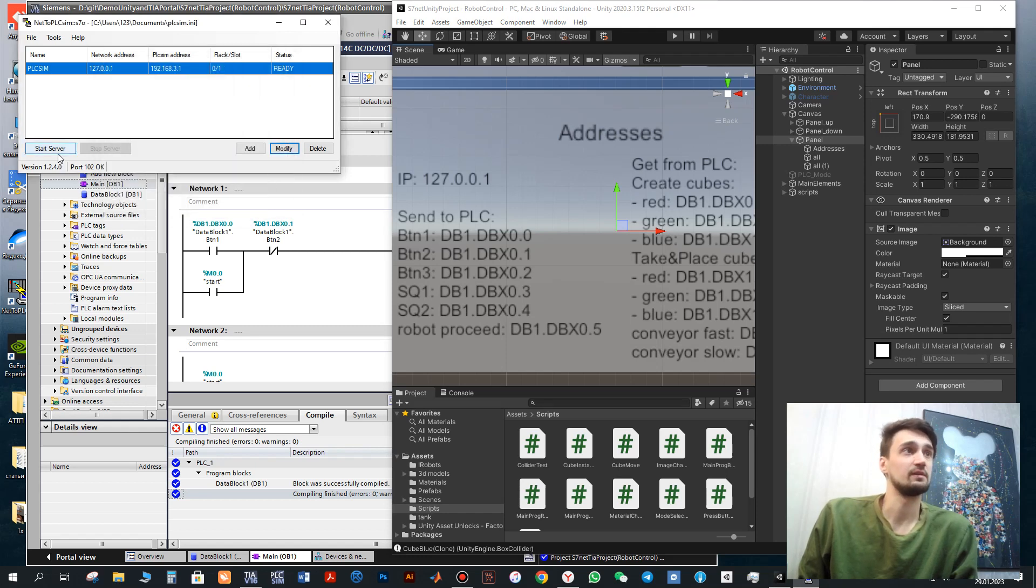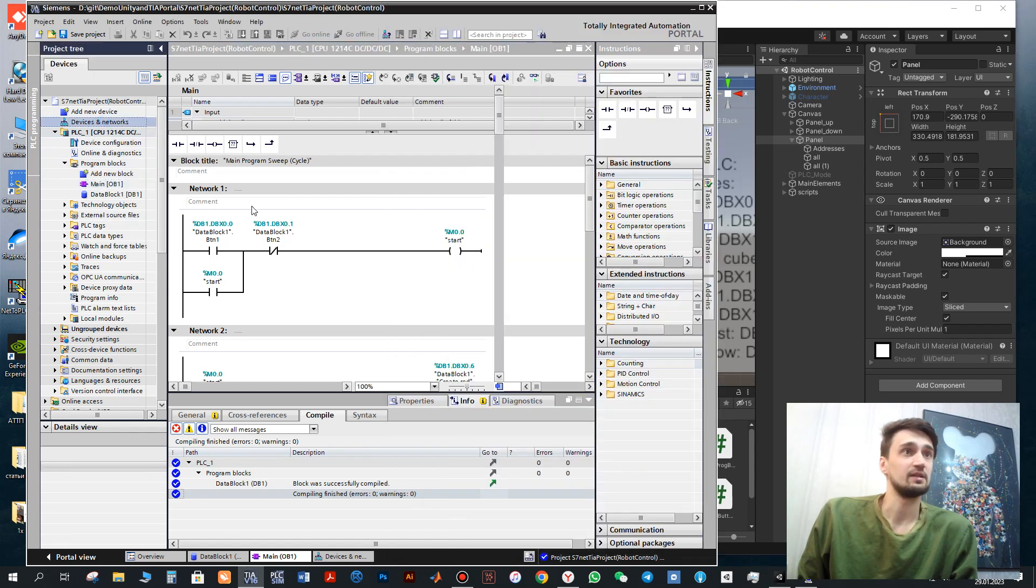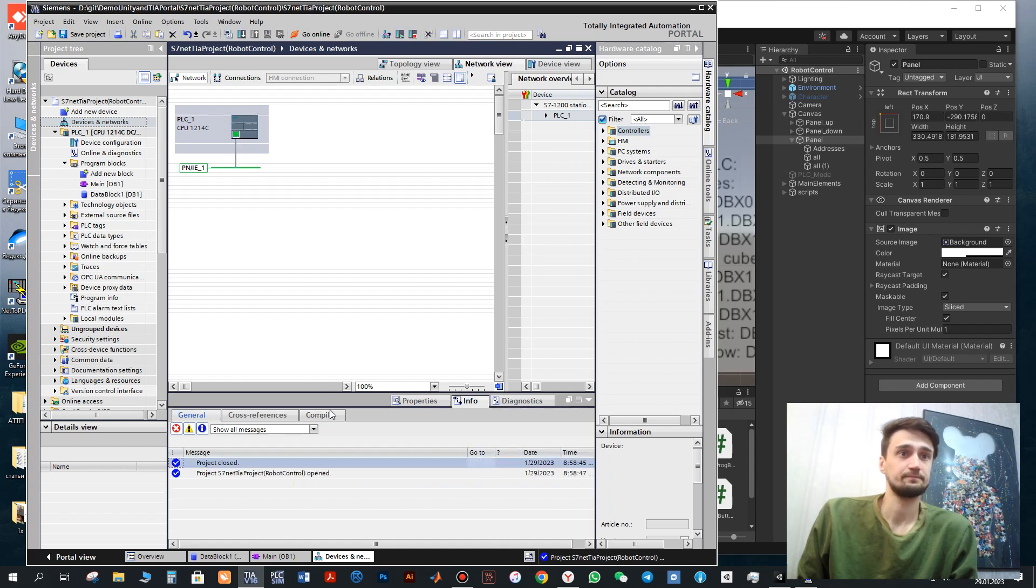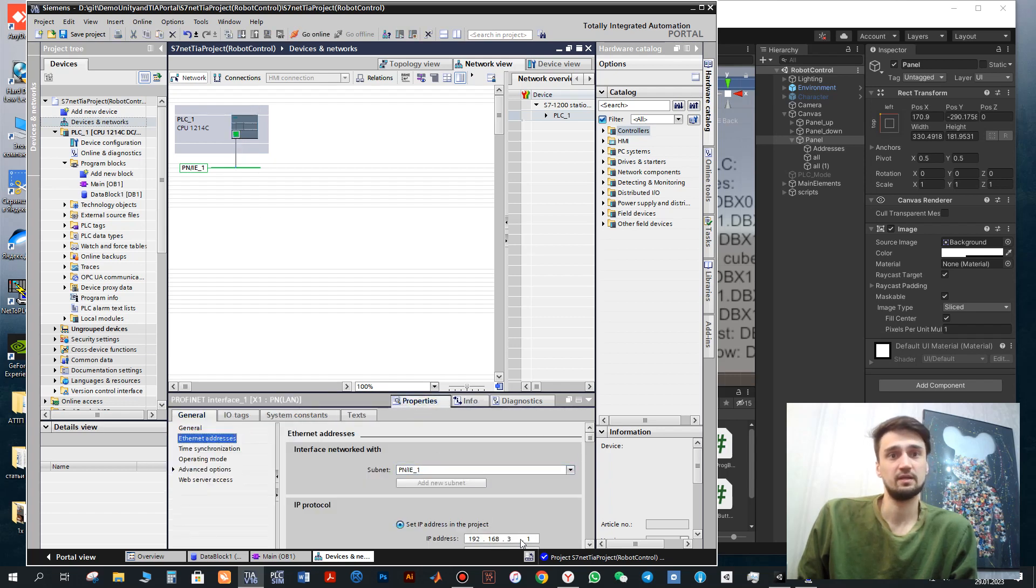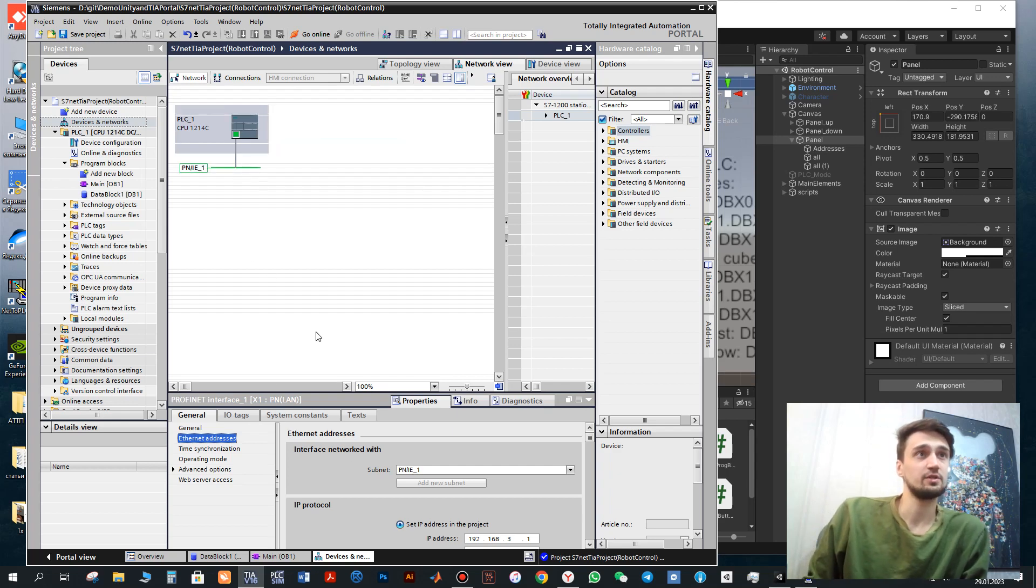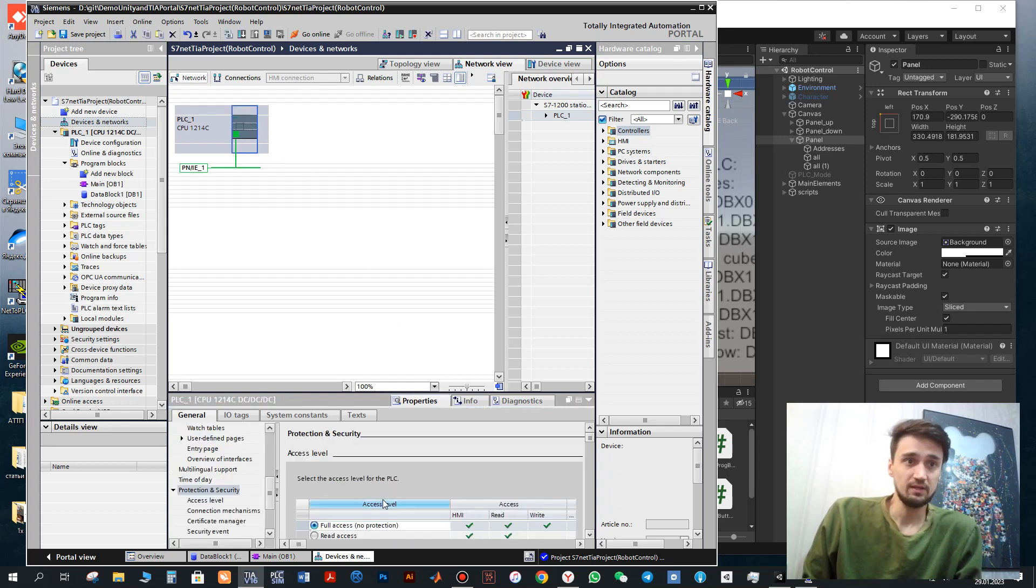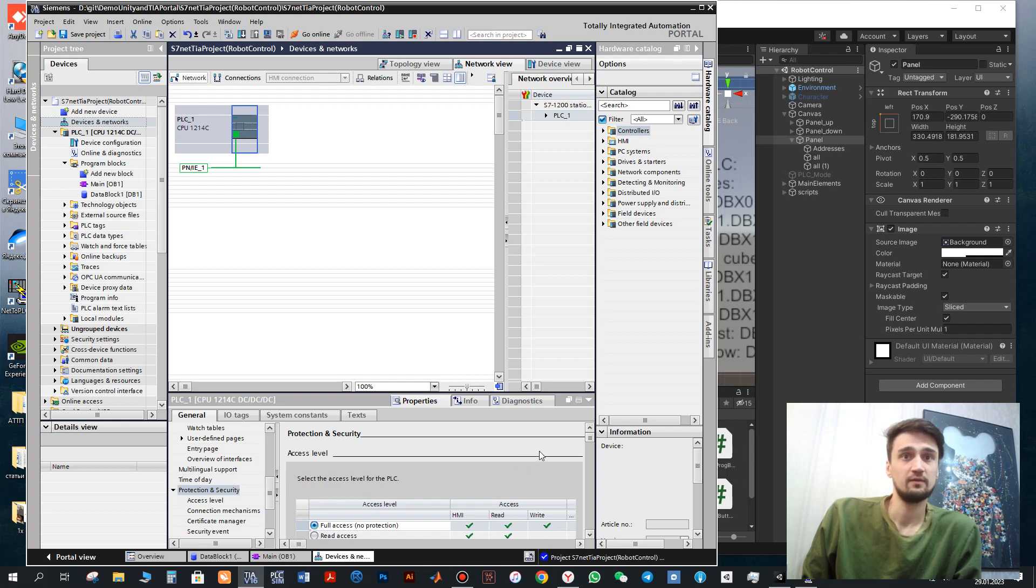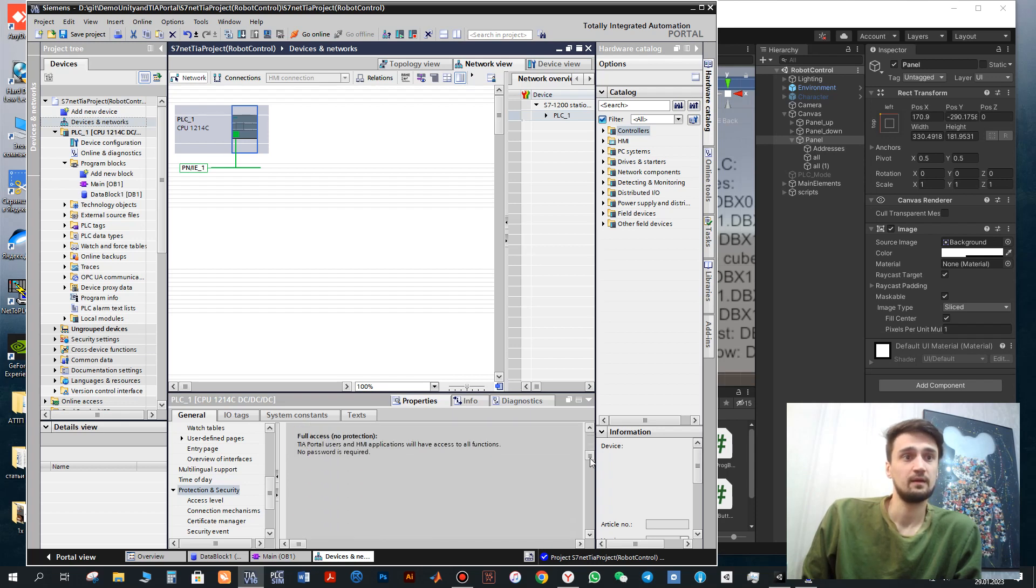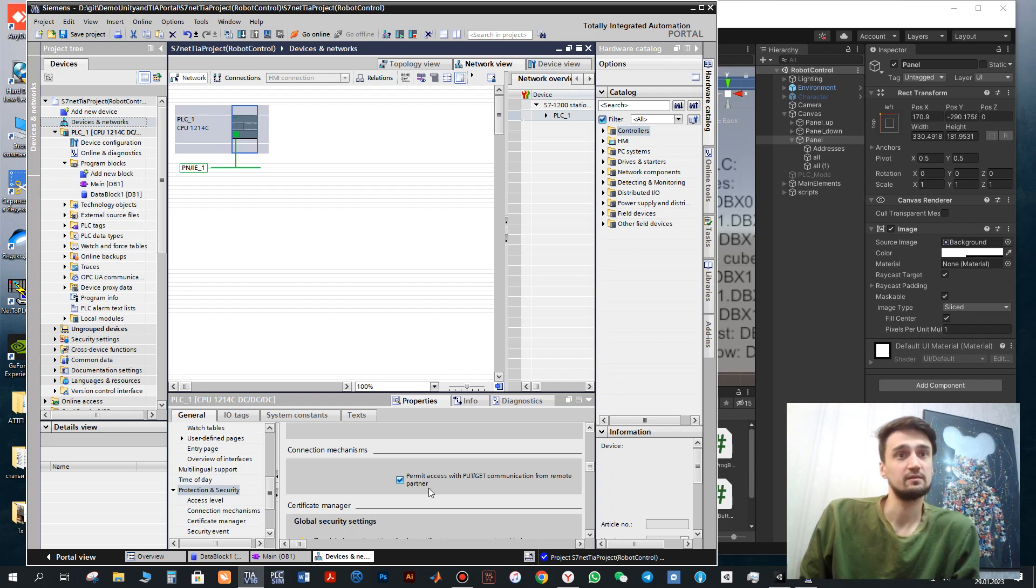After that we simply start this server. And address of the PLC you can check here: device and networks. So you set it up here. This is your IP address. And when you create new project in order to communicate between TIA Portal and Unity, you need to make sure that it's full access here. And also activate this toggle: permit access with, for this communication.